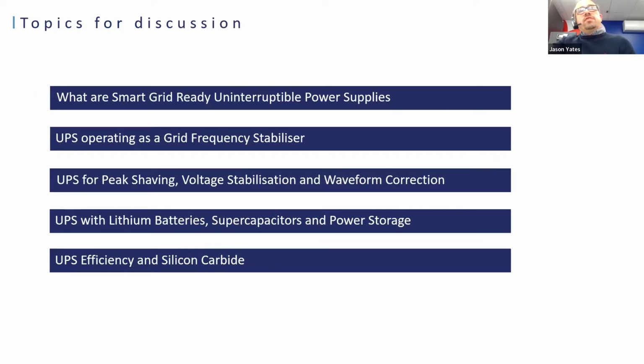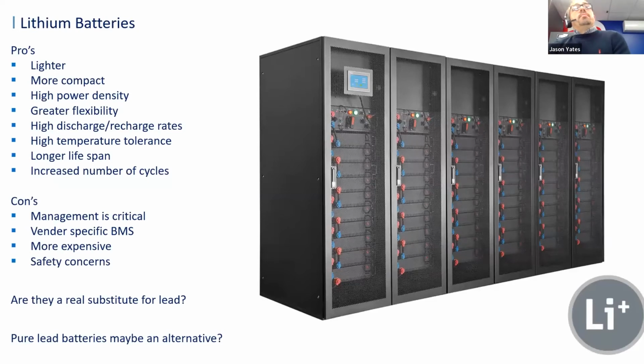One of the upcoming things: typical UPS systems at the moment are most commonly supplied by lead-acid batteries, but we are now making the move to look at alternative technology in terms of lithium batteries and supercapacitors being utilized for power storage. Now, this is a typical lithium battery system that we supply. Obviously, lithium batteries are improving all the time. There are some pros and cons for lithium batteries. Pros: they're lighter, more compact, and have higher power density and greater flexibility. They can have high discharge and recharge rates, they can operate at high temperature tolerances, and they have a longer lifespan and increased number of cycles.